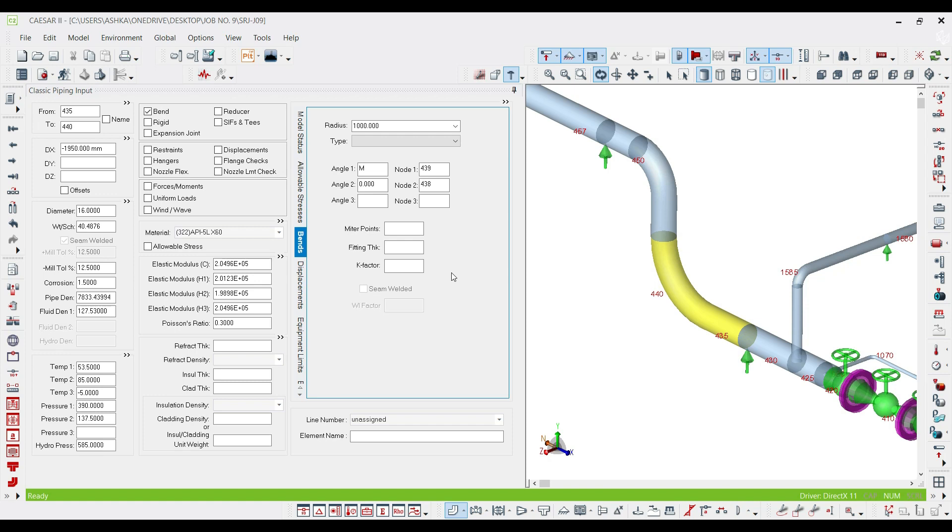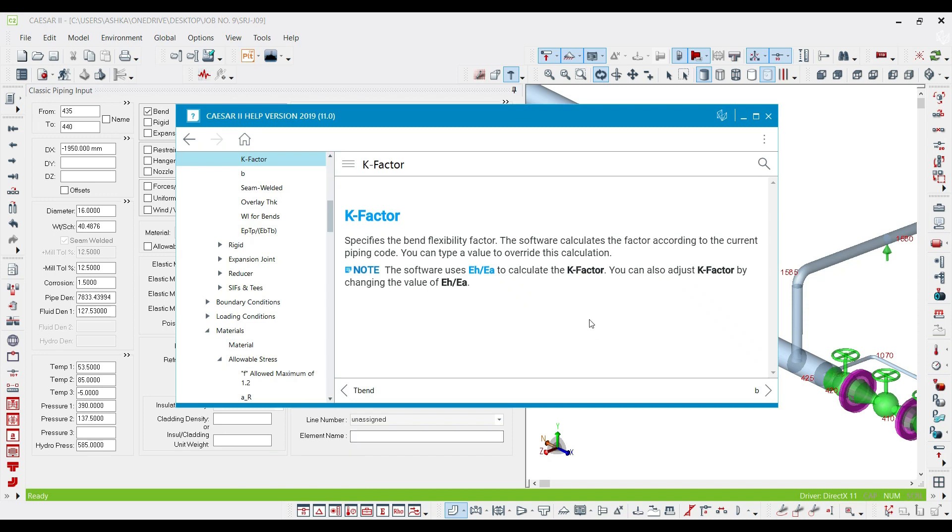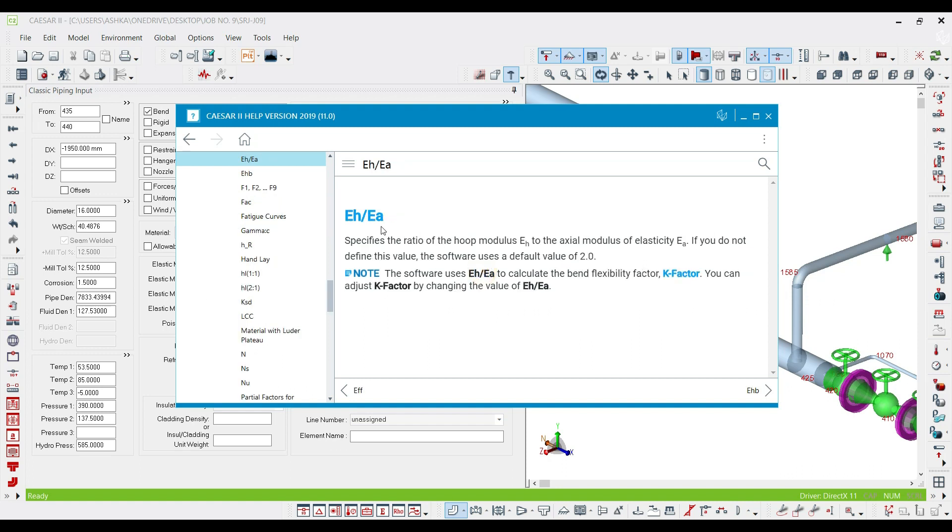The final item that I'm going to describe is the K factor, which is considered as the flexibility of your elbow. If you press F1, you can see the help of the software. The K factor is bend flexibility factor, which is considered by default equal to EH to EA. The first item is hoop modulus and the second one is elastic modulus, axial modulus of elasticity.